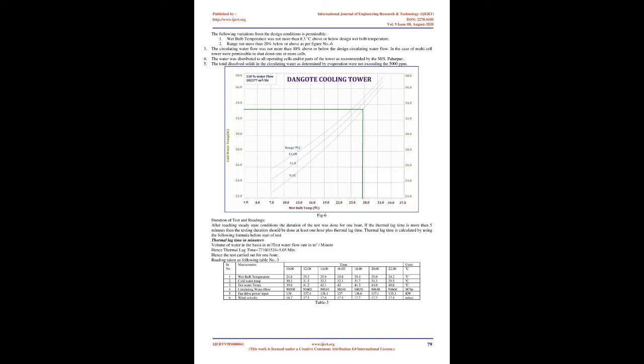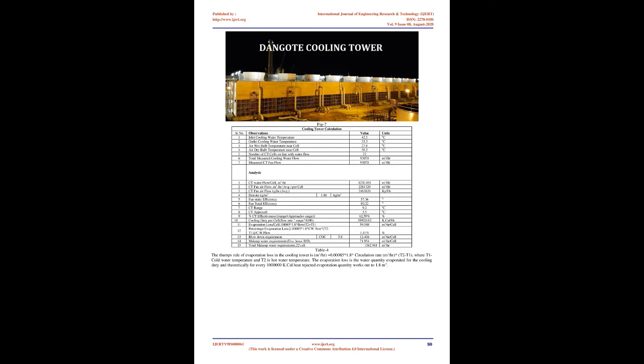5. CW outlet temperature at full bottom, using accurate mercury in glass or a digital thermometer. 6. Process data on heat exchangers, loads on line or power plant control room readings, as relevant. 7. CW flow measurements either direct or inferred from pump motor kW and pump head and flow characteristics. 8. CT fan motor amps, volts, kW, and blade angle settings. 9. TDS of cooling water. 10. Rated cycles of concentration at the site conditions.